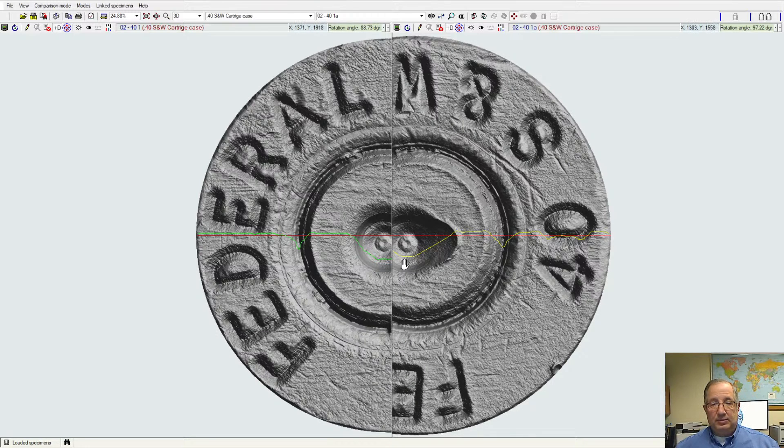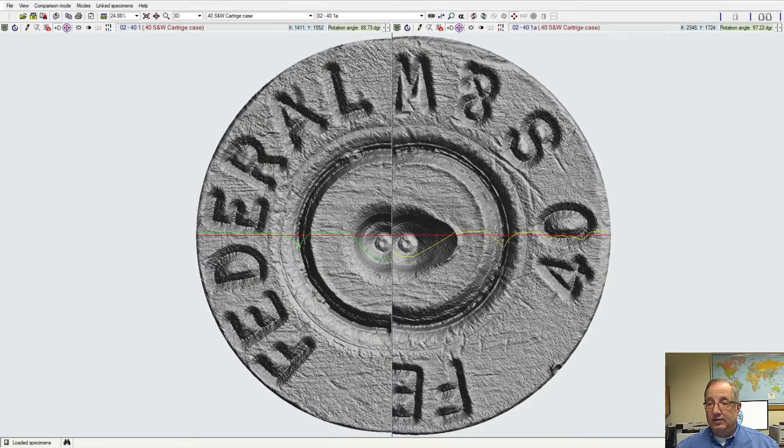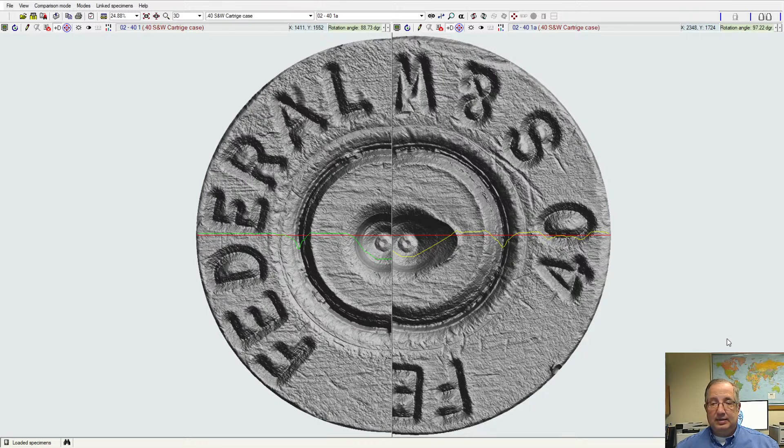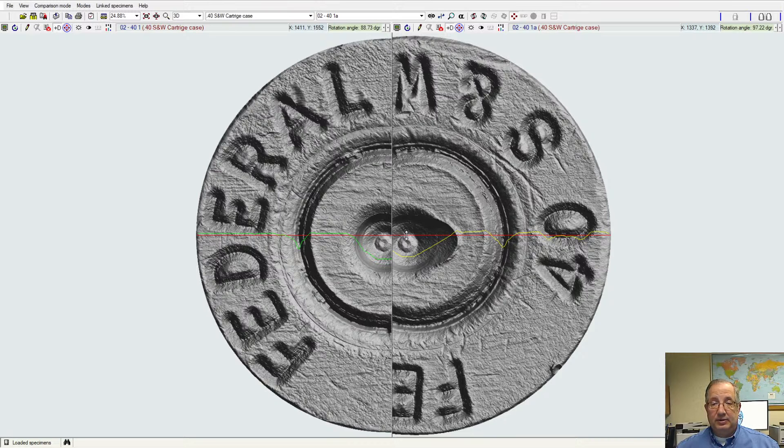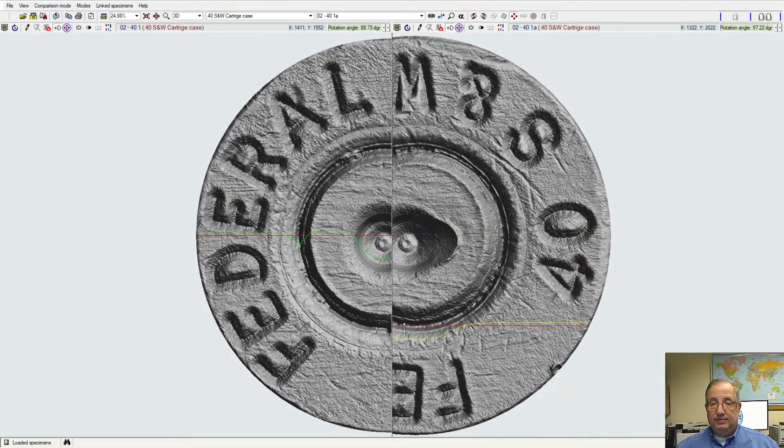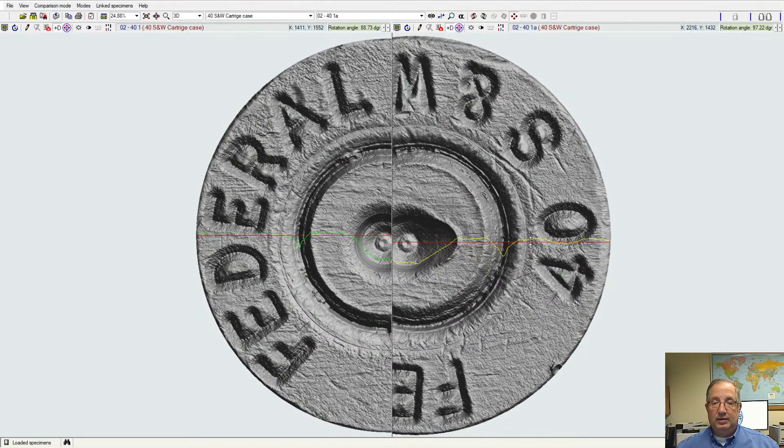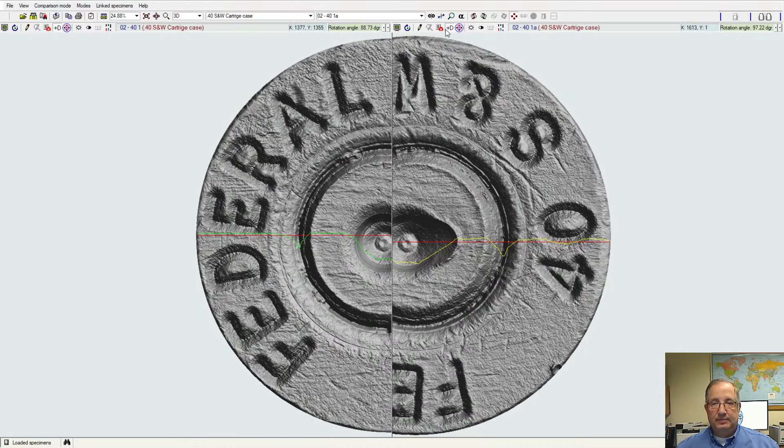On the sample image, I have a green line on the left and the yellow on the right that shows the cross-sectional depth profile. Or if I use the sub-windows, I can tilt this back and I can see that sample tipped back in the Z axis and show the cutoff where that red line is on my sample image. If I grab that red line, I can also take it and move it to different regions on the sample so I can get a good look at the cutoff of the depth profile where that red line occurs on my sample image.